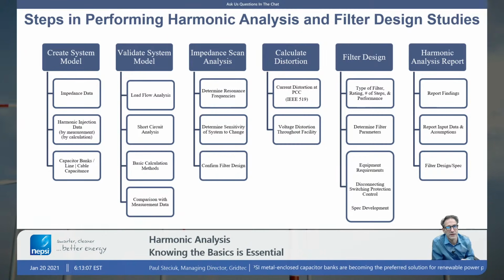We're going to talk about impedance scans as an important part of harmonic analysis, interpreting impedance scans. If you've ever seen a harmonic study, a lot of times it's full of various impedance scans. So we're going to talk about how to read those and what the significance of those are. Harmonic calculation of current distortion and voltage distortion, another key thing. Remember, we're looking to improve the power quality within the plant, to keep the voltage distortion, say, down below 5%.